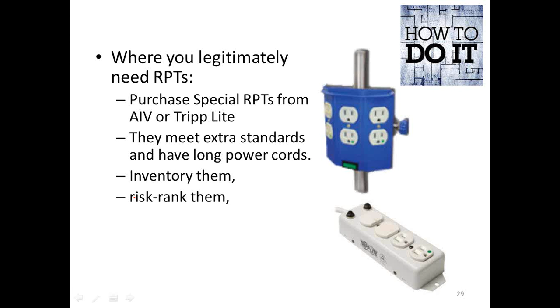You can risk rank them, applying the same risk criteria you'd use for any other piece of patient care equipment in the hospital, but I suspect you'll need to test them at least once per year, including the electrical integrity of the power and ground, as well as the mechanical integrity of the tension of the outlets. Then put them on your PM schedule and test them when you test everything else.